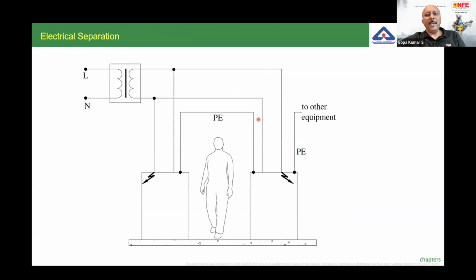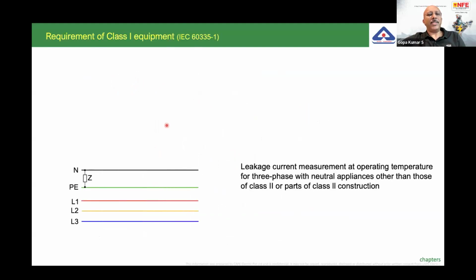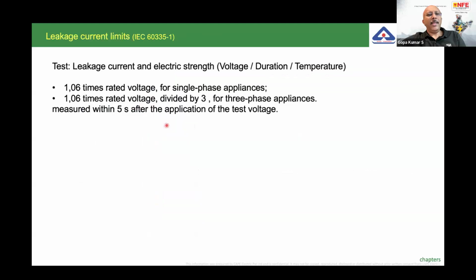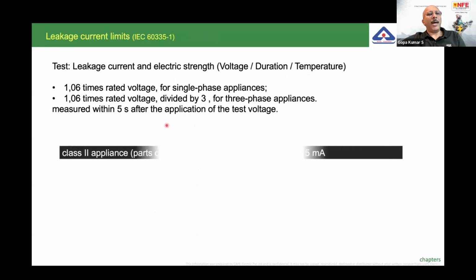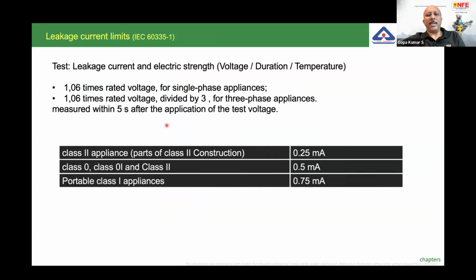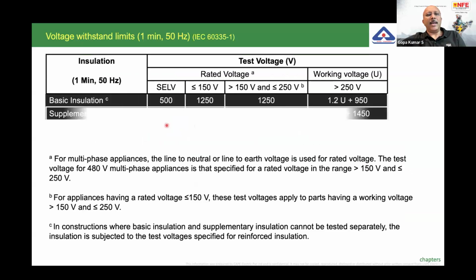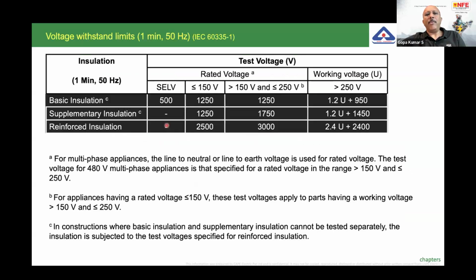Similarly, electrical separation. Electrical separation means, imagine you have a machinery. The input supply of the machinery is going through an isolation transformer into this particular equipment. Even during the first fault, people don't get shock because the secondary side of the isolation transformer is insulated. So these are some of the safety measures included in the standard. And you can see very well that the equipment are tested, for example for basic insulation, the leakage currents are tested. The continuous voltages are applied for certain time and tested. So basically, class 1 equipment as per the standard means all these tests are already made.